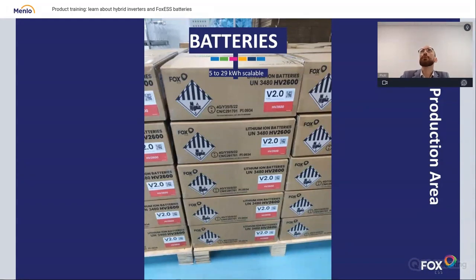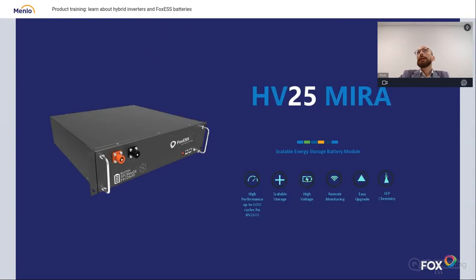So let's talk about battery and battery system and battery stacks and where to put those batteries, how to connect them, what they can offer. This is a HV25 Mira battery. It's a standard modular battery. This module can be placed in a 19-inch cabinet. We have some cabinets manufactured by other partners, but I'm pretty sure that if you have any 19-inch rack cabinet, teletechnical power cabinet, you can place those batteries there. They are about 2U of size. So for a working system, you will probably need 10 or 12U of that cabinet.